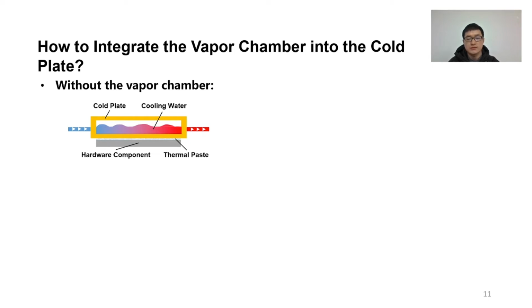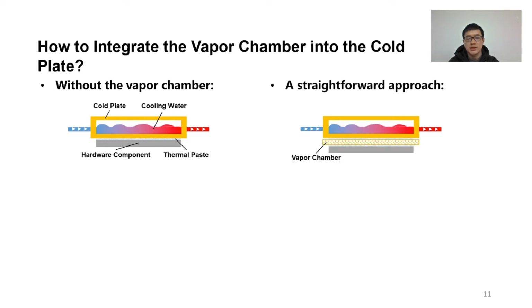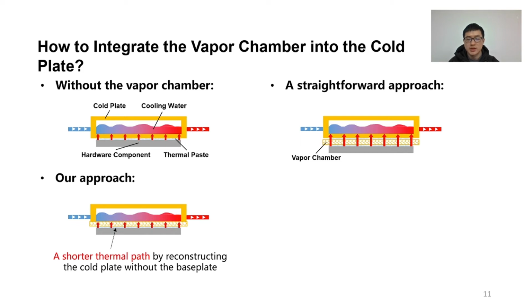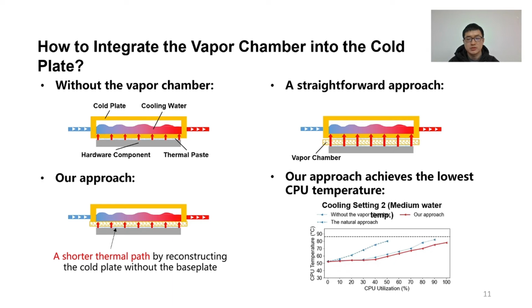A straightforward idea for the integration of the vapor chamber might be directly inserting the vapor chamber between the hardware component and the cold plate with an additional layer of thermal paste. However, we find this is exceedingly inefficient in transferring heat due to the much longer thermal path. Instead of attaching the vapor chamber to the bottom of the cold plate, we replace the cold plate's base plate with the vapor chamber for achieving a short thermal path. To verify the effectiveness of our approach, we conduct an experiment to compare the CPU temperature when using the different approaches. From the cooling setting of low water temperature to high water temperature, our approach keeps outperforming the others.